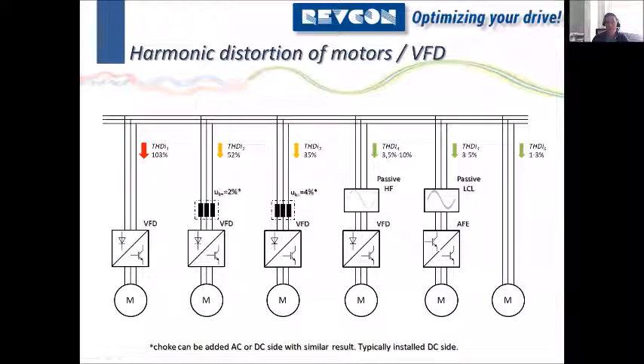So starting with something simple, if we look at different drives and different drives input current, we should know that if we have a drive that has no input choke on it, just a simple rectifier, we will see a harmonic distortion somewhere above 100%. In this example, it's 103%, can go up to 110. It can be 95 if you're lucky, but in any case, it will be very, very high. So means the harmonic part is roughly the same as the fundamental part.